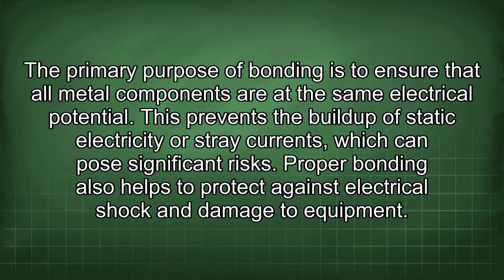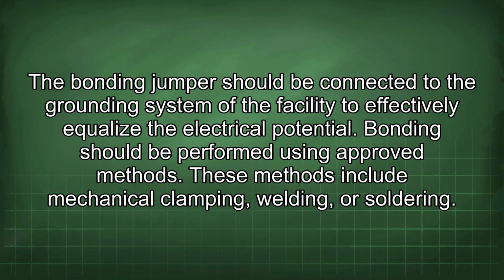This prevents the buildup of static electricity or stray currents, which can pose significant risks. Proper bonding also helps to protect against electrical shock and damage to equipment. The bonding jumper should be connected to the grounding system of the facility to effectively equalize the electrical potential.